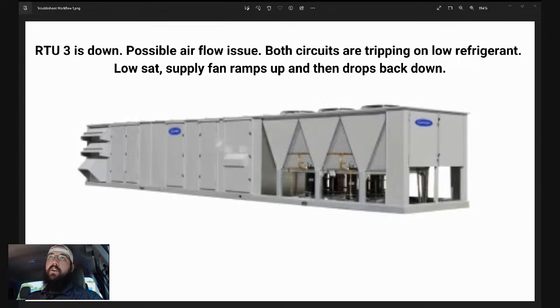So that's one of the things with 30 hertz, you're running at the drive's basically minimum speed. You really shouldn't see that drive get down to or below 30 hertz very much or very often. And typically the only time it's going to, or it should, is if there's a really low load scenario. Now, let me take a step back. One of the things that's really easy to do is get tunneled into a possible refrigerant issue. And we spend so much of our time, so much of our day trying to evaluate refrigerant circuits that it's easy to let that kind of take over the focus of what you're working on.